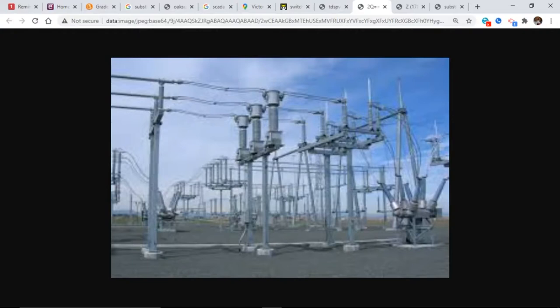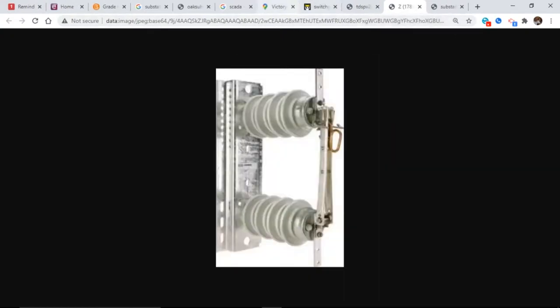So I've got tubular coupled with strain. Now, the reason why they're doing this here is tubular is carrying the high amperage, but if I ever need to get it, this is kind of a manual way to do it. What do I need to have if I want to work on this thing? Two visual open points. I'm able to disconnect here. Now I've got an air gap in between and I've got two visual open points. So even though it's not customary by a switch, I'm still able to fulfill the safety needs to be able to take care of it. Okay, so that was bus.